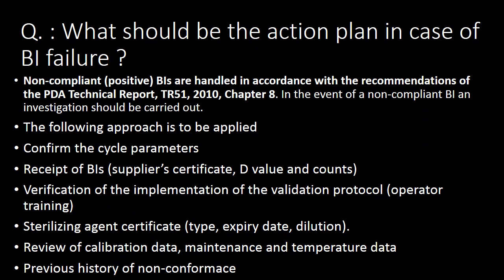Next very important question: what should be the action plan in case of biological indicator failure? Non-compliant or positive BIs are handled in accordance with the recommendations of PDA Technical Report Number 51, Chapter 8. In the event of a non-compliant BI, an investigation shall be carried out.